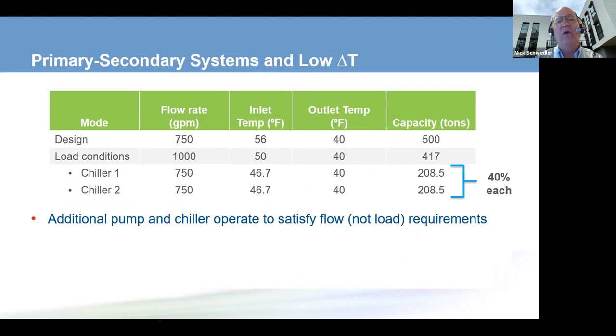The problem is we're not getting the full delta T out of the coils. So the water is returning at 50 degrees, and the load, because we're only getting a 10 degree delta T at those coils, we need 1,000 GPM. Well, in a primary secondary system, the flow rate through each chiller is constant. So if we only have 750 GPM of flow, we end up having deficit flow in the bypass line.